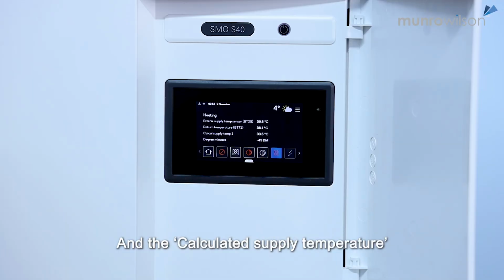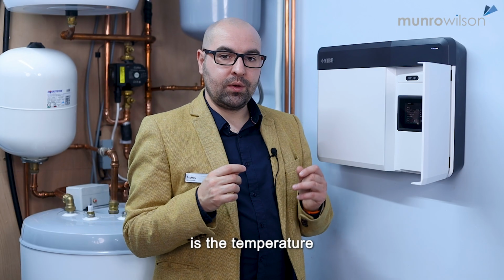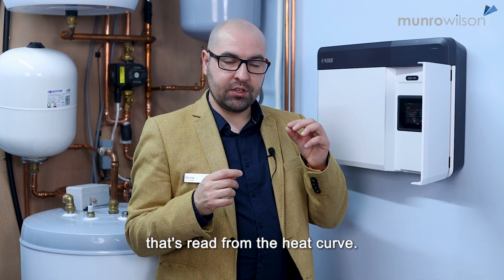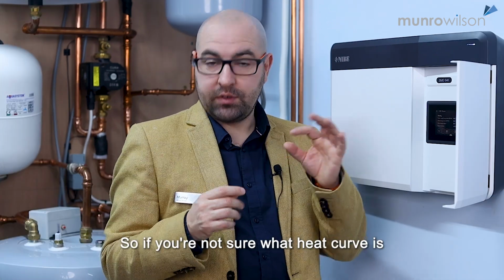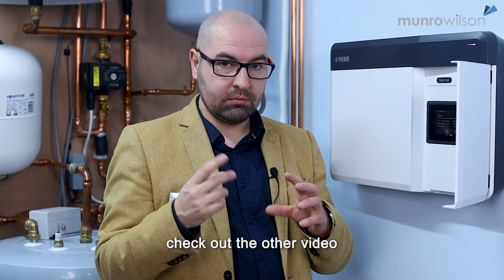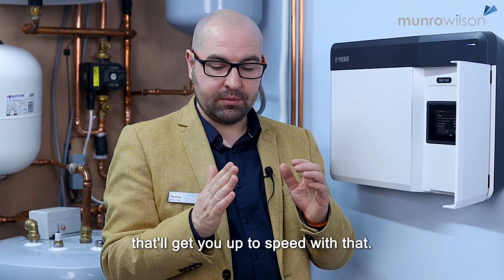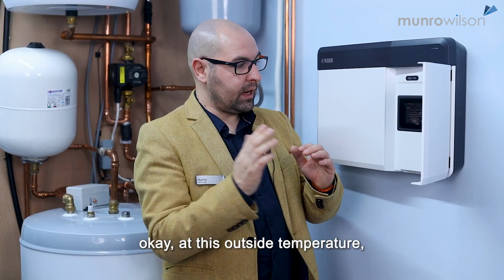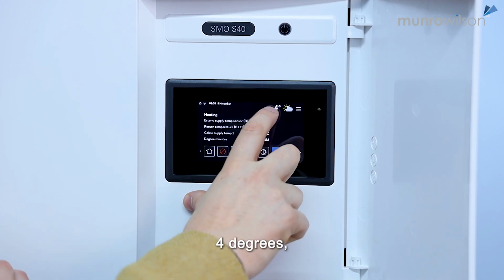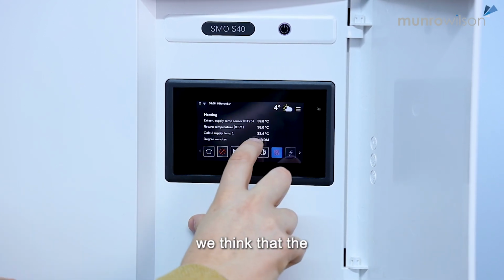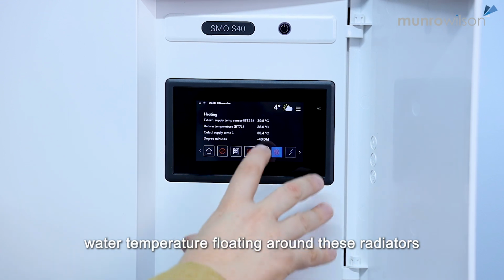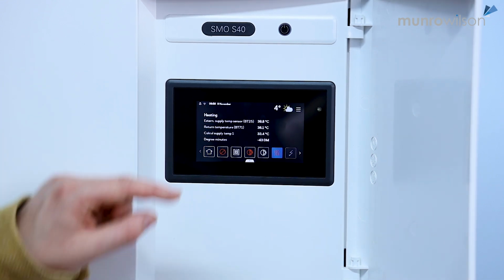And the calculated supply temperature is the temperature that's read from the heat curve. So if you're not sure what a heat curve is, check out the other video, that'll get you up to speed with that. But the heat curve is saying, okay, at this outside temperature, 4 degrees, we think that the water temperature flowing around these radiators should be 33.4.